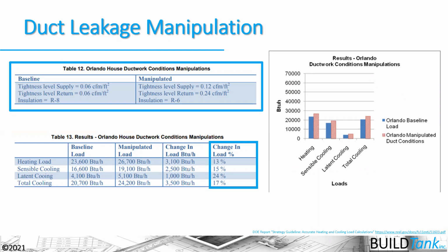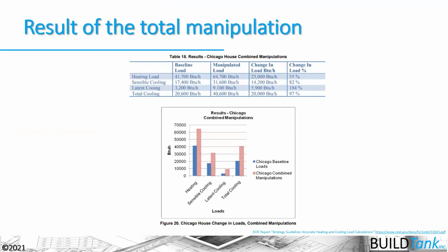You can see the heating load impact of 13% and the cooling load of 17%. And then what we ultimately see is how all of these things result in the total manipulation. So if you add up all of those different changes, those 8 things, we get a heating load that's 55% off and a total cooling load that's almost 100% off. And if you're in a warm, humid climate, that latent cooling load is almost 184% off. You know, we're getting to the point where we are hugely, grossly oversizing or undersizing our equipment, depending on how it goes. But it's not right. It's not right size. We're not going to get a system that's efficient. We're not going to get a system that works and performs for that house here.